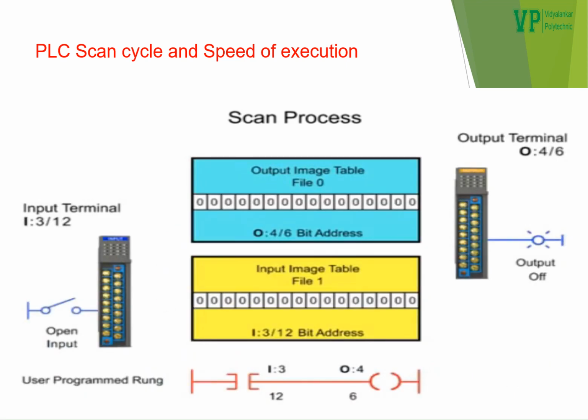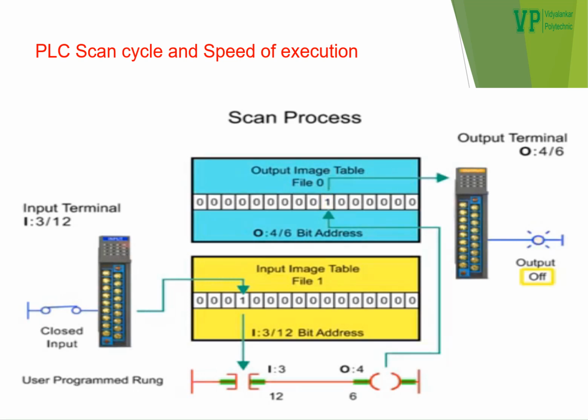When the switch is closed, the information of the switch position gets updated in the input status table. During the program execution phase, the instructions get executed one by one, and depending upon the status of the input status table, the output status table gets updated. During the last phase of scan, that is, update output status, the status of the output gets reflected in the output, and it energizes or de-energizes the output accordingly.